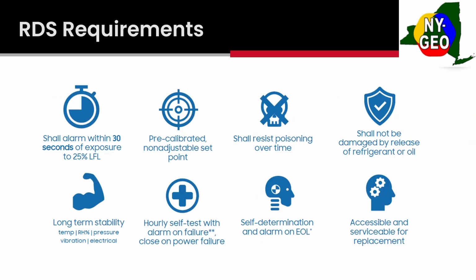So the RDS requirements. If the RDS goes off, the alarm is going to go off within 30 seconds of exposure. These sensors are also pre-calibrated. They cannot be adjusted in the field. You cannot modify them. They come as they are. Shall resist poisoning pretty much means they're not going to degrade over time. If there is a refrigerant leak, they're not going to get damaged. They're still going to work. Long-term stability just means under the right conditions, it's still going to work. So temperature, relative humidity, pressure, all that, the RDS is still going to work.